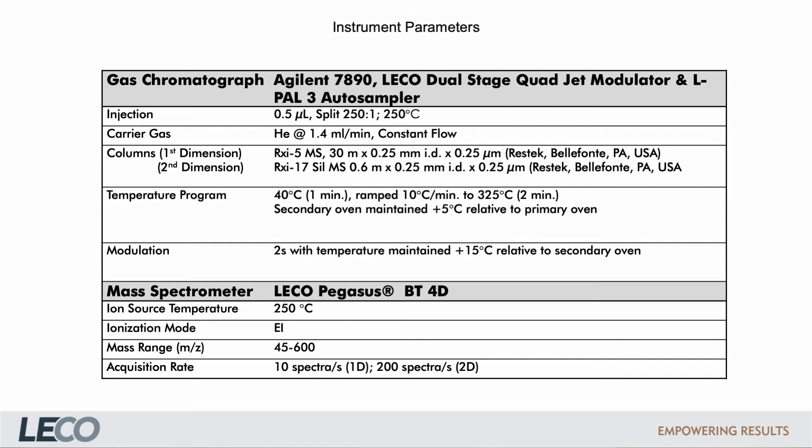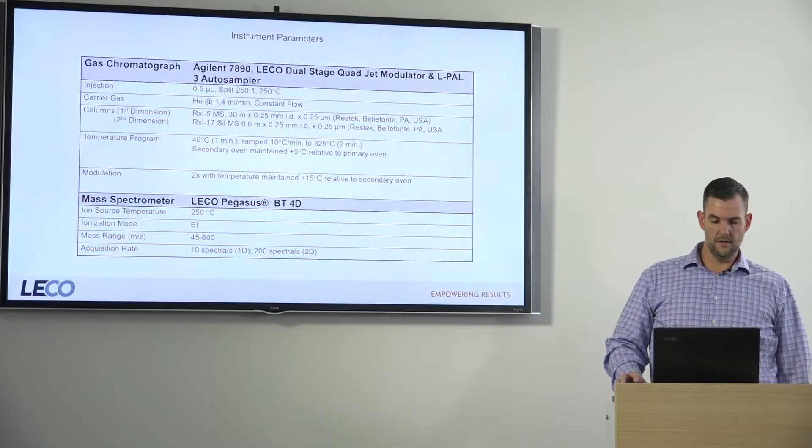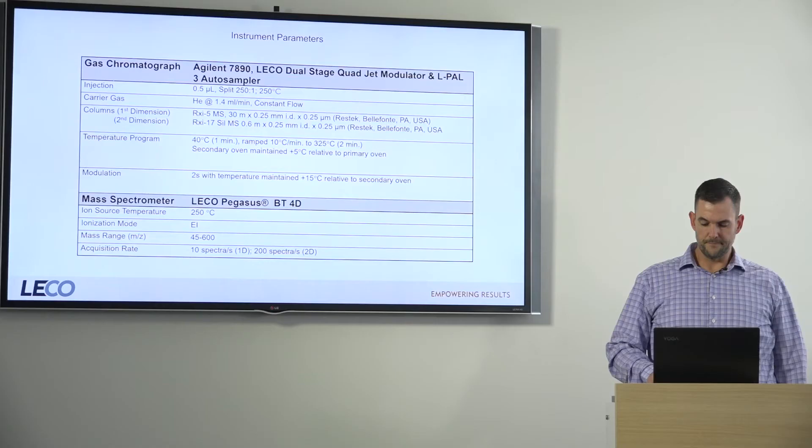The mass range acquired was 45 to 600. Our acquisition rates were 10 spectra per second for the 1D experiments and 200 spectra per second for the 2D experiments. The acquisition rate of 200 spectra per second is important for GCxGC because you end up with very narrow second dimension peaks, and you need high acquisition rates to generate enough data points to appropriately define the peak shape.